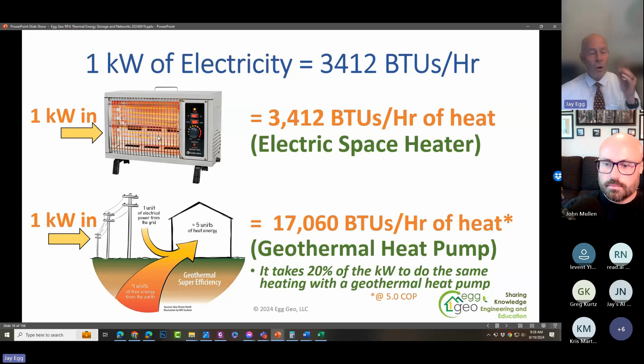It's not using that electricity to burn to make heat. Rather, it's using that electricity to run a heat pump, pumping heat out of the ground in this case. So for 1 kilowatt of electricity, we can pump 4 units of heat out of the ground for a total of 17,000 BTUs per hour of heat. That's 5 times the amount of heat you can get from an electric resistance heater, which plays into what we're going to talk about in the next slides.